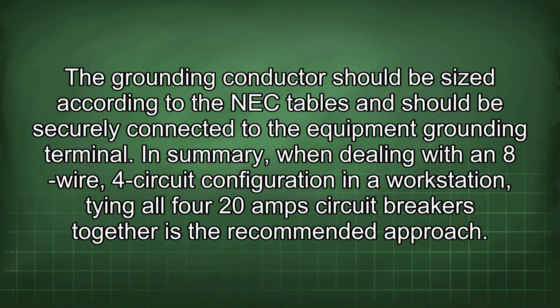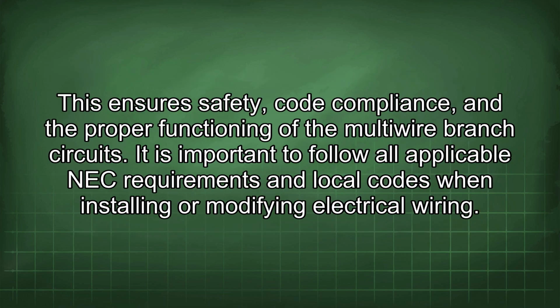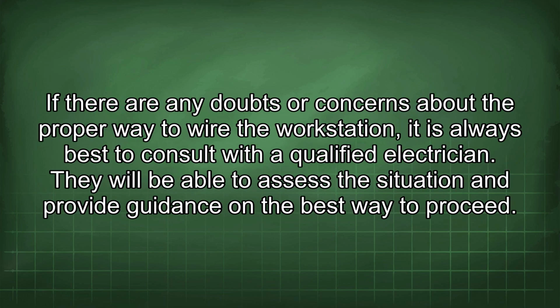In summary, when dealing with an 8-wire, 4-circuit configuration in a workstation, tying all 4 20-amp circuit breakers together is the recommended approach. This ensures safety, code compliance, and the proper functioning of the multi-wire branch circuits. It is important to follow all applicable NEC requirements and local codes when installing or modifying electrical wiring.